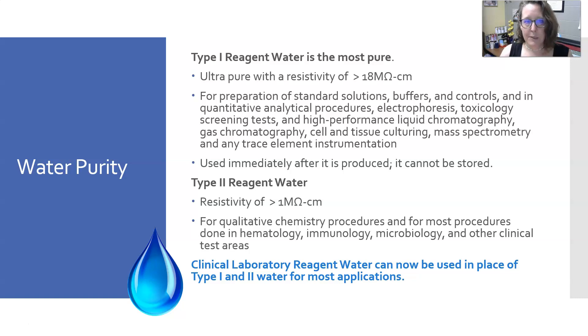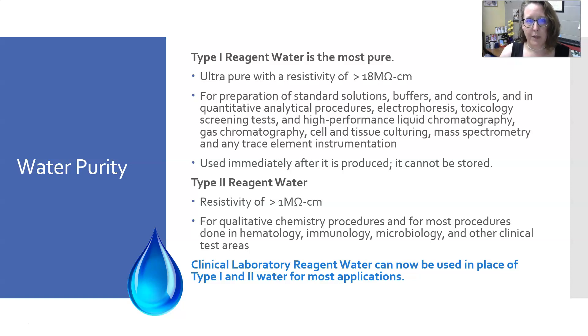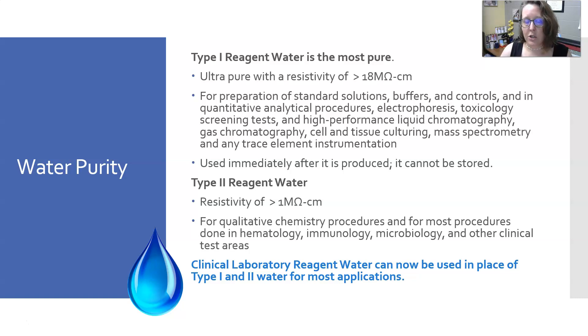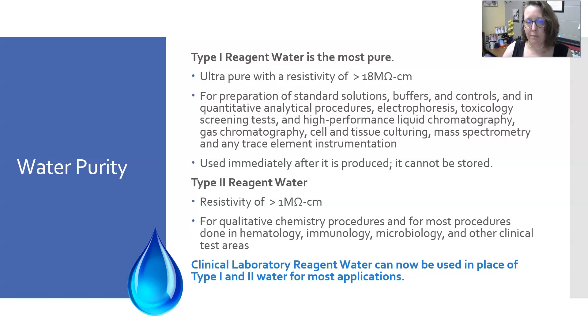Water can also be classified as Type 1, Type 2, Type 3, and even Type 4 based on purity. Type 1 reagent water is the most pure — it is considered ultra-pure, with a resistivity of greater than 18 mega-ohms per centimeter. It is used in the preparation of standards, buffers, controls, and quantitative analytical procedures, as well as in electrophoresis, toxicology screening, high-performance liquid chromatography, gas chromatography, cell and tissue culturing, mass spec, and any trace element instrumentation. It must be used immediately after it is produced and cannot be stored.